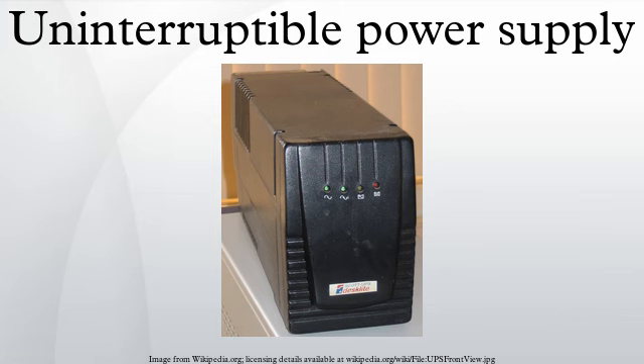Distribution of UPS status and control data requires that all intermediary devices such as Ethernet switches or serial multiplexers be powered by one or more UPS systems, in order for the UPS alerts to reach the target systems during a power outage. To avoid the dependency on Ethernet infrastructure, the UPSs can be connected directly to the main control server by using a GSM GPRS channel also. The SMS or GPRS data packets sent from UPSs trigger software to shut down the PCs to reduce the load.